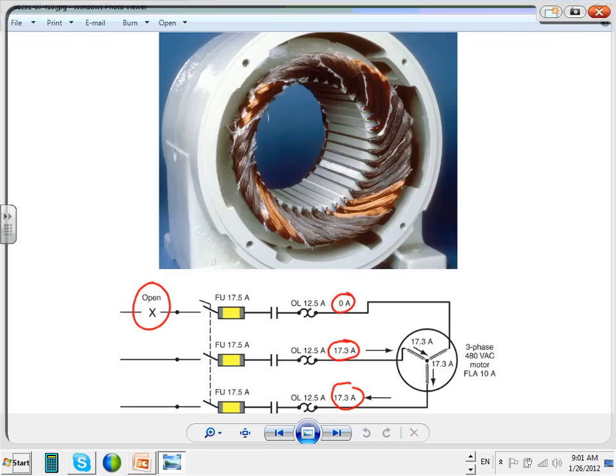17.3, do you think the fuse will protect you here? The fuse would never open. Remember, we size the fuses at 20 amp, yeah. 20 amp, 20 amp. And I'm pulling 17.5. Would it even wake up? No. So the only one that is going to wake up and protect you in this situation is a properly sized overload protection. So you can protect from overload and you can protect from single phasing. What's single phasing? When you lose a phase or two on a three-phase system.